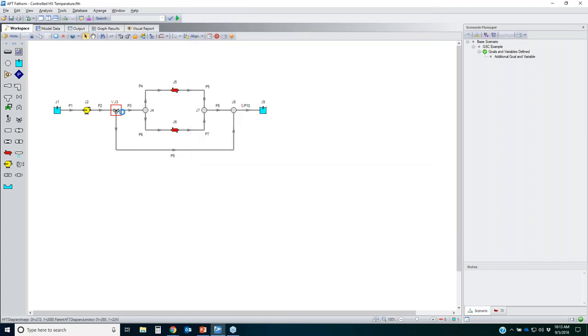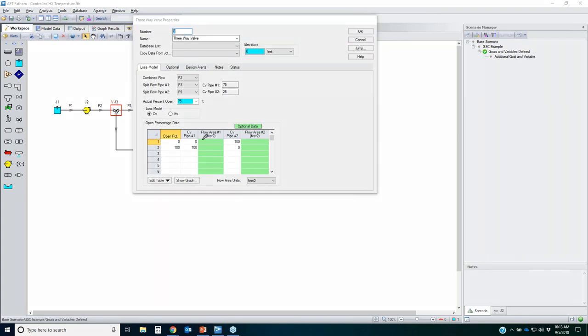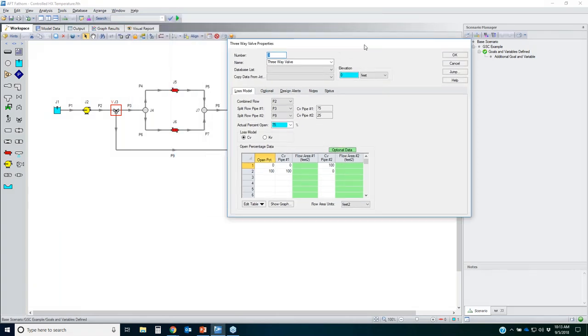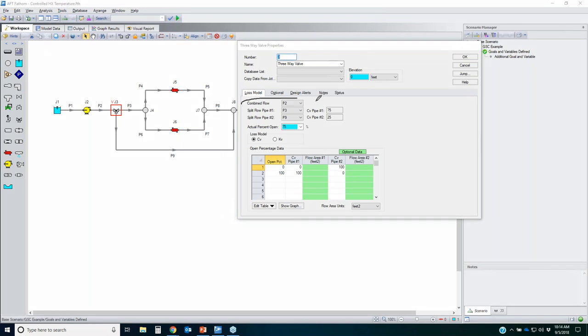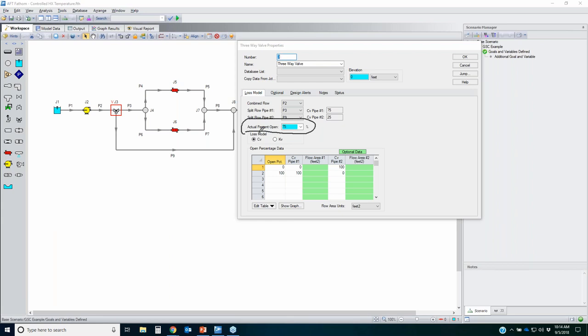For the three-way valve, you define an open-percent versus Cv table. You specify the Cv profile for each split-flow pipe, so the model knows which pipe is favored. After setting up that table, you specify the actual percentage open for your three-way valve. This is just a starting guess because GSC is going to change that parameter — without GSC, you'd have to manually iterate the open percent, which could take a long time depending on system complexity.